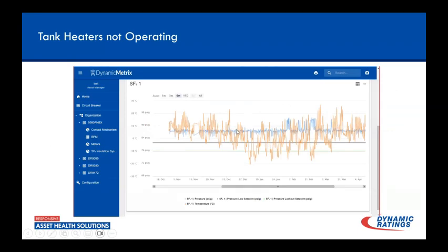So this was another slide that was captured from data from an online monitor. And I wanted to show this. It's not a waveform capture per se by testing, but we were talking about SF6 and how temperature affects these, and the things we can see when we start plotting out these various values.